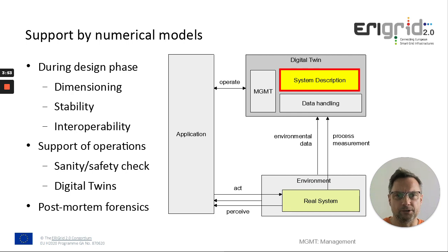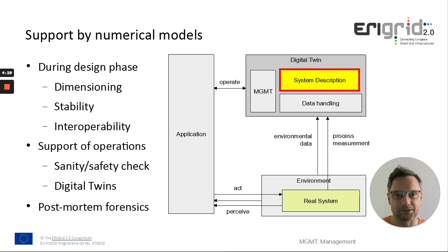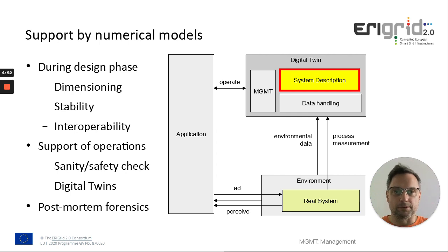During the design and planning phase, you can use such a model for dimensioning assets, for stability analysis. You can go through certain scenarios, check for interoperability — especially when it comes to controls. How do different controllers interact? This is something you almost cannot calculate analytically anymore and you need numerical methods. During operation, this model can also be useful. You can check it for plausibility — if you have a model following reality in real time, deviations might point to a problem. You can fast-forward into the future and check for robust operational decisions, and you can also use them for post-mortem analysis.